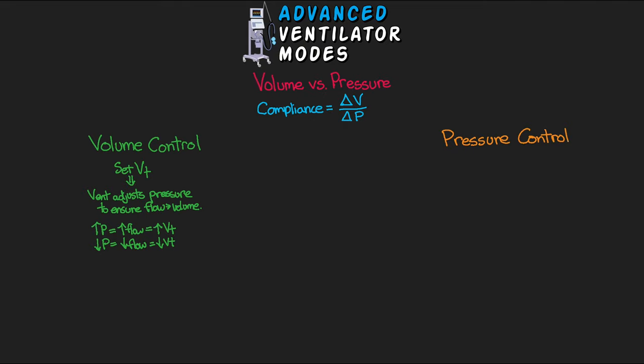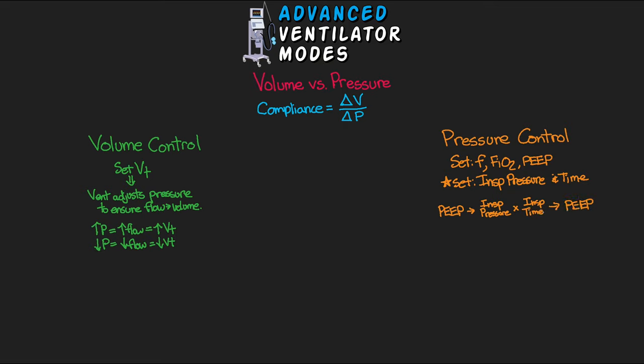In basic pressure control we set a frequency, an FiO2, a PEEP, an inspiratory pressure, and an inspiratory time. What's happening is the vent switches from our PEEP level up to our inspiratory pressure and holds that for the set inspiratory time, then drops back down to PEEP. For example, with a PEEP of 5 and an inspiratory pressure of 20, the vent holds at PEEP, then increases to 20 for the inspiratory time, then drops back down.